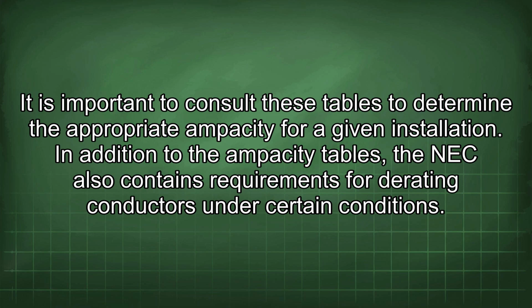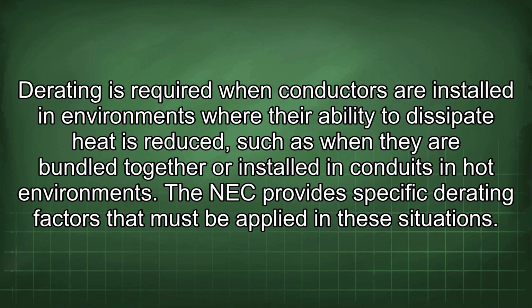In addition to the ampacity tables, the NEC also contains requirements for derating conductors under certain conditions. Derating is required when conductors are installed in environments where their ability to dissipate heat is reduced, such as when they are bundled together or installed in conduits in hot environments. The NEC provides specific derating factors that must be applied in these situations.